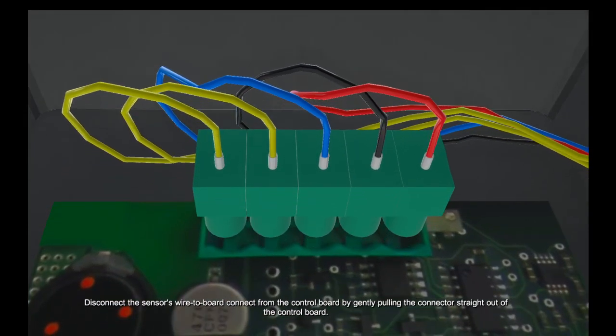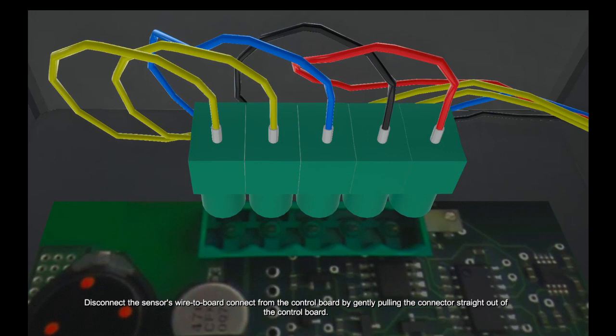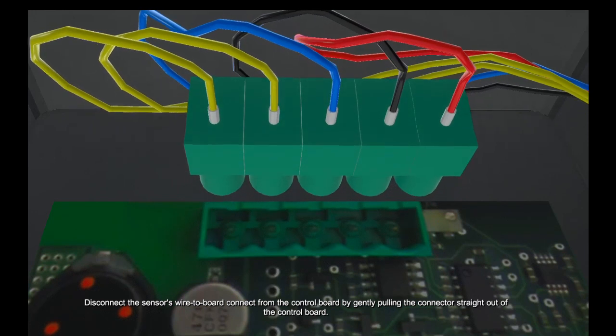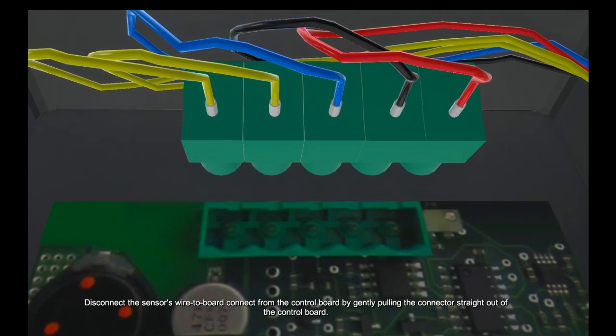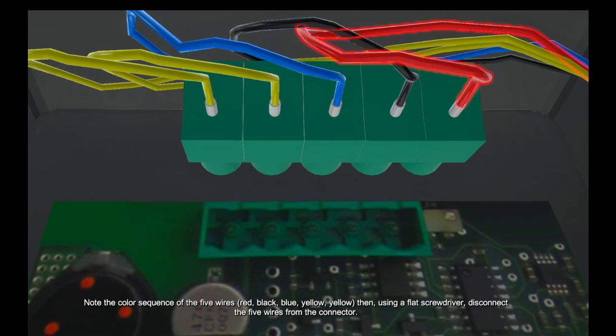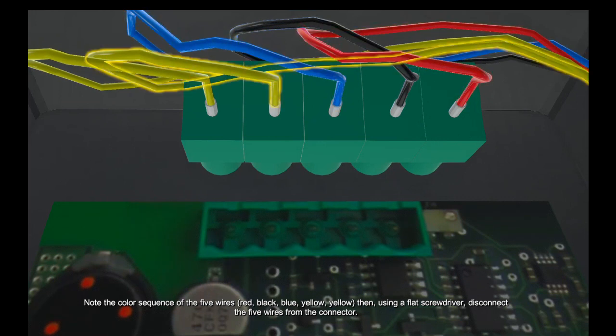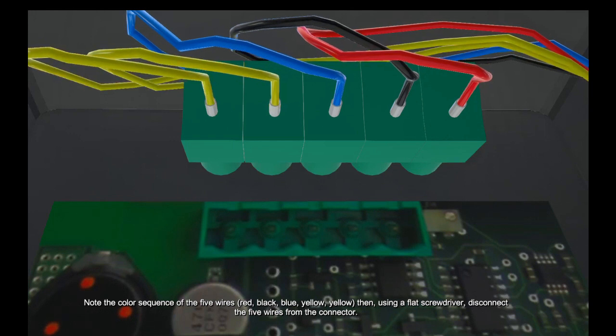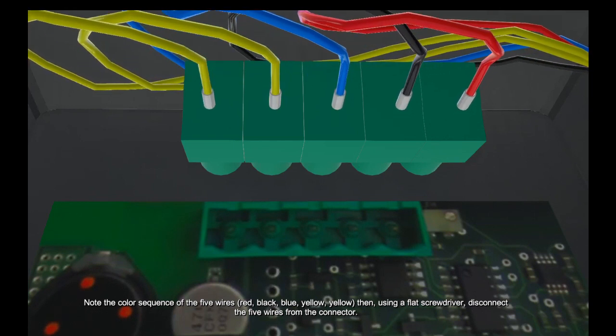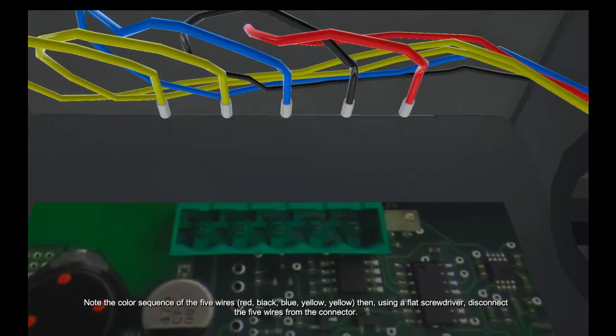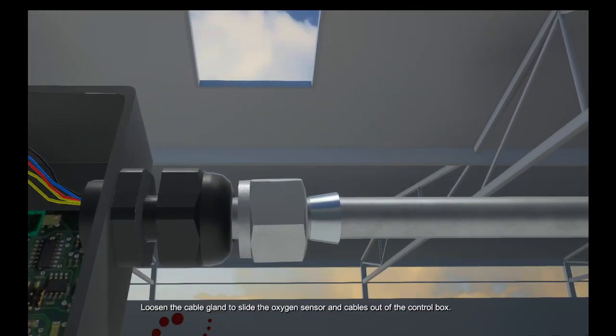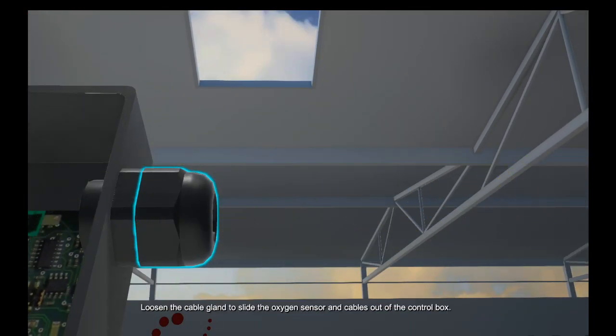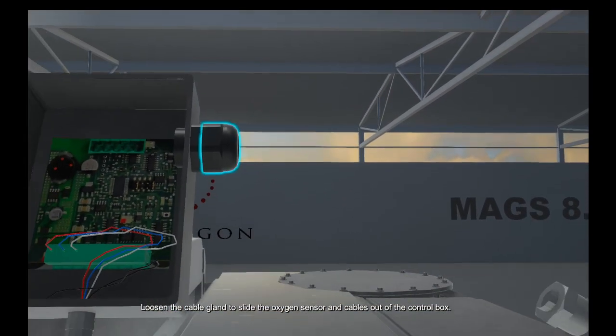Disconnect the sensor's wire-to-board connector from the control board by gently pulling the connector straight out of the control board. Note the color sequence of the 5 wires: red, black, blue, yellow, yellow. Then, using a flat screwdriver, disconnect the 5 wires from the connector. Loosen the cable gland to slide the oxygen sensor and cables out of the control box.